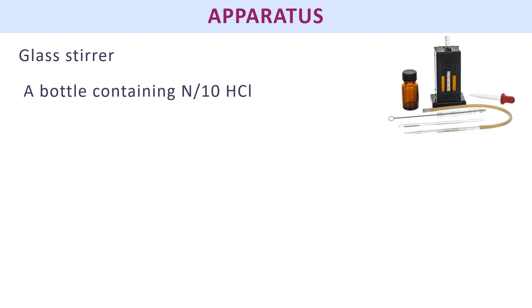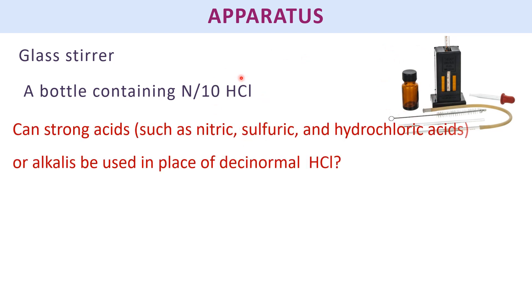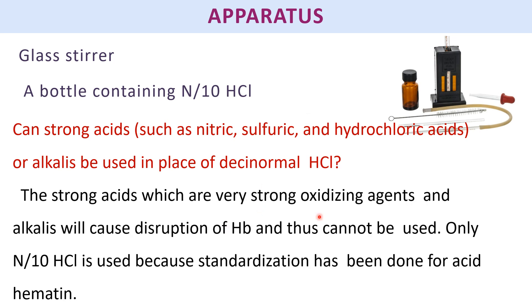Finally, there is the glass stirrer and a bottle of N/10 HCl. An important question: why must N/10 HCl be used — can strong acids like nitric acid or sulfuric acid be used instead? The answer is no: strong acids are oxidizing agents that can disrupt hemoglobin. N/10 HCl is used because the standardization is also done using N/10 HCl to produce acid hematin.